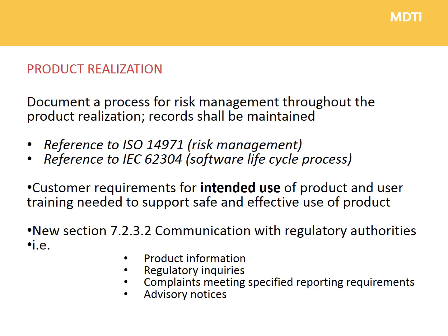So we have a specific reference in the text, normative reference in the text of the new 13485 document to ISO 14971 risk management. So we've got that tie-in explicitly there. Now, interestingly, we also have a specific tie-in to IEC 62304, which is about software lifecycle processes. That's very interesting because there's a much increased emphasis on software documentation and testing development in the proposed text of the new regulations, and that's reflected here.